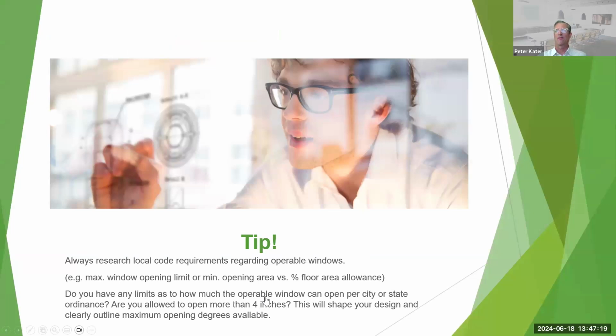Code requirements affect the way we design buildings with natural ventilation technology incorporated into them. And this includes the requirements that apply to operable windows specifically. This includes things such as window opening limit, or the minimum opening area versus the floor area allowance. This, in turn, needs to be considered when you're designing a natural ventilation system, because it could limit the amount of free area that the windows will be allowed to achieve. And that means also limiting the amount of fresh air that can be drawn in.